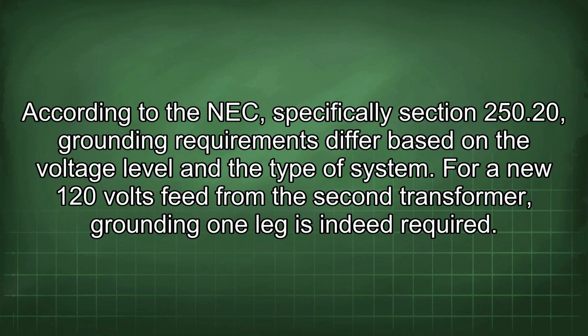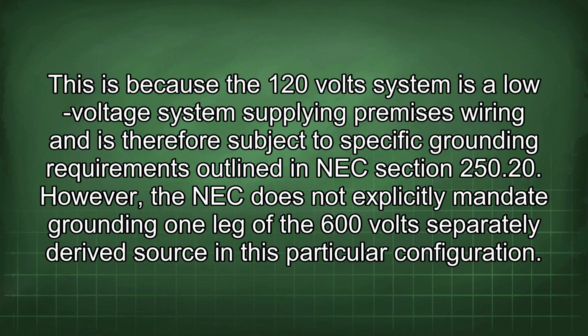According to the NEC, specifically Section 250.20, grounding requirements differ based on the voltage level and the type of system. For a new 120 volts feed from the second transformer, grounding one leg is indeed required. This is because the 120 volts system is a low voltage system supplying premises wiring and is therefore subject to specific grounding requirements outlined in NEC Section 250.20.